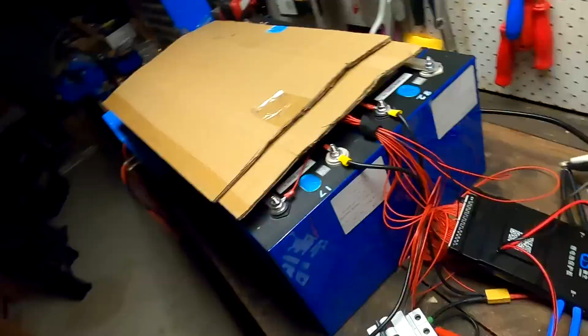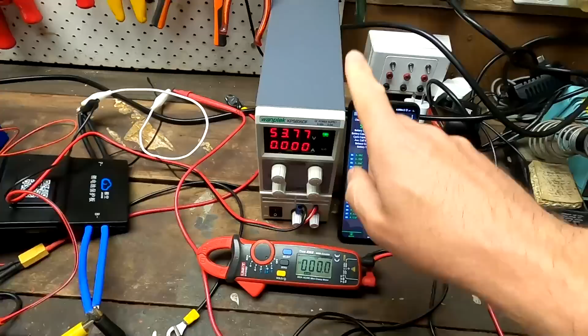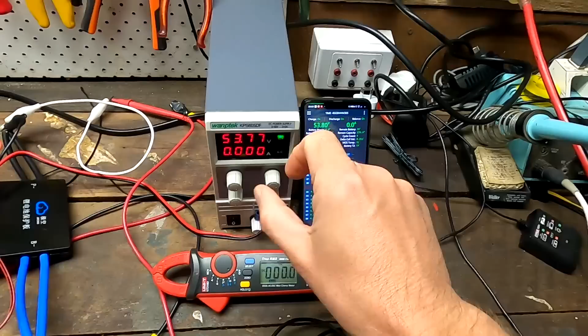So basically, how I understand it is we have got 2 rows of MOSFET transistors in here. One is for charging, one is for discharging - no, it's the other way around, doesn't matter. So they are wired the other way around, basically. If one is conductive, the other one is not conductive, unless it is turned on in the app. If it's not conductive, it is like a PN junction, and we will have the 0.6 volt across this PN junction. That's why we need the power supply roughly 0.6 volt higher than the battery voltage to see a charge. If the voltage difference is small, so if you reach your absorption voltage, for example, and the voltage of your battery and charge controller is very close together, you can get into this trouble.